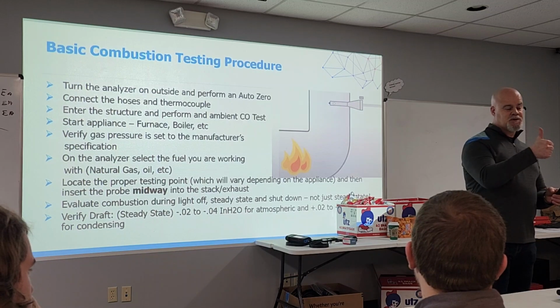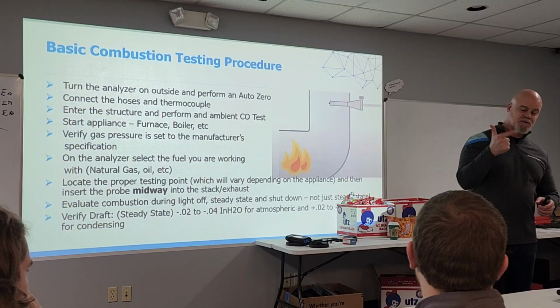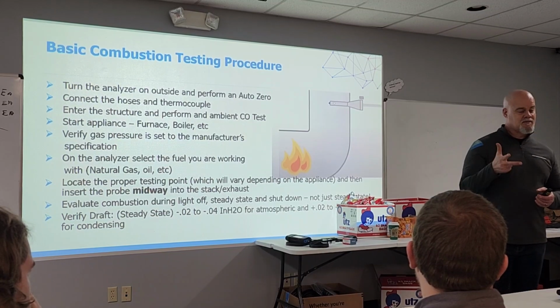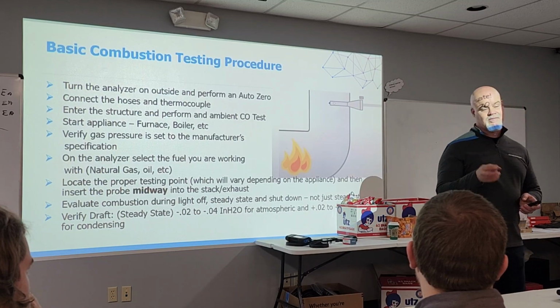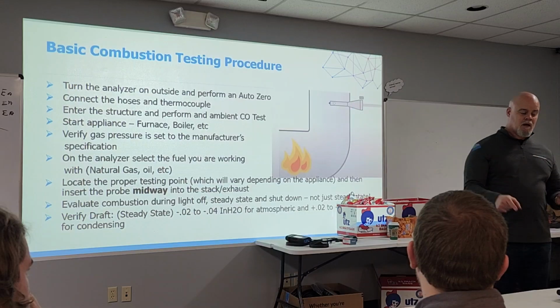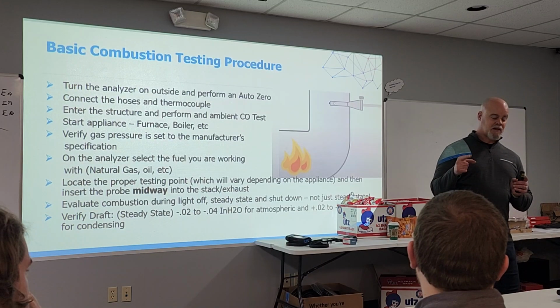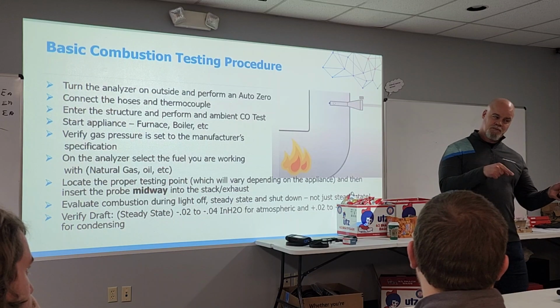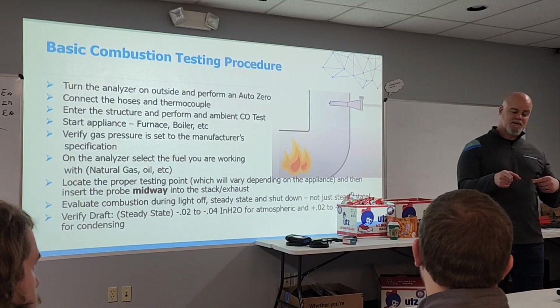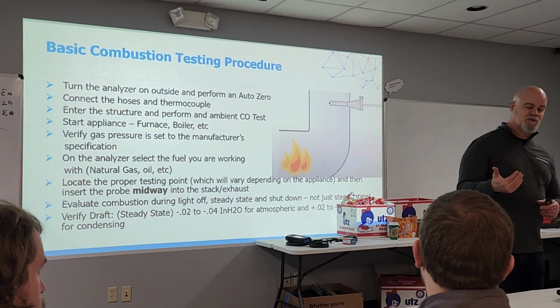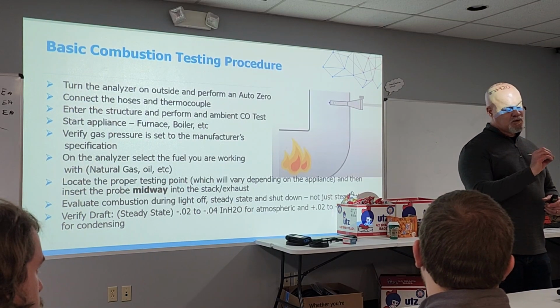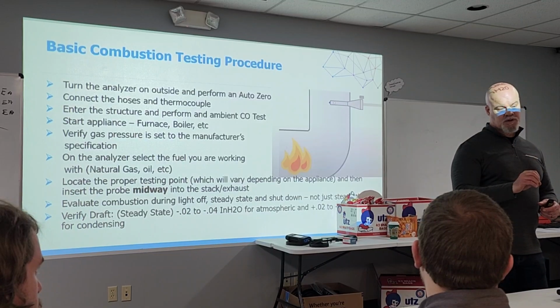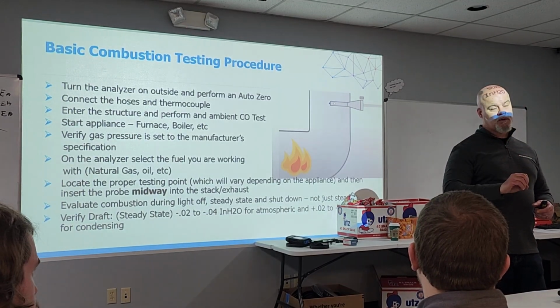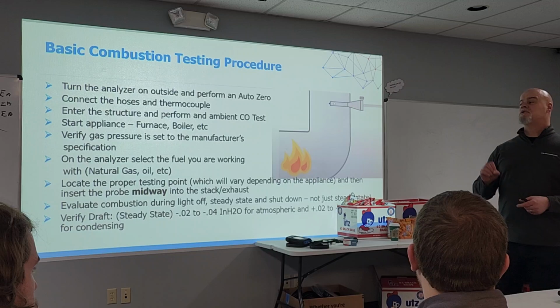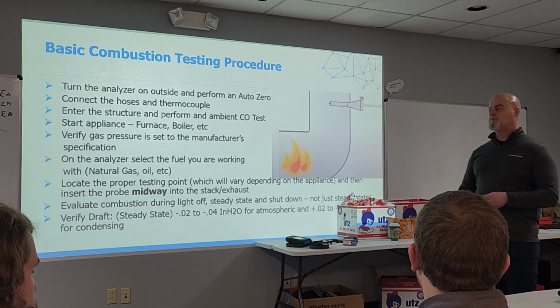You have an oxygen sensor in your analyzer? Yes, you do. You have a CO sensor? Yes, you do. But you do not have a CO2 sensor because it is a calculated value. And again, it is calculated by taking the coefficient of the fuel, that long decimal number, multiplying it by the percentage of oxygen. The resulting answer to said math is what gives you your CO2 value. So if your fuel selection is off, your CO2 is gonna be off, and your efficiency is gonna be off, and some other things are gonna be off. So please make sure you select the correct fuel going forward.